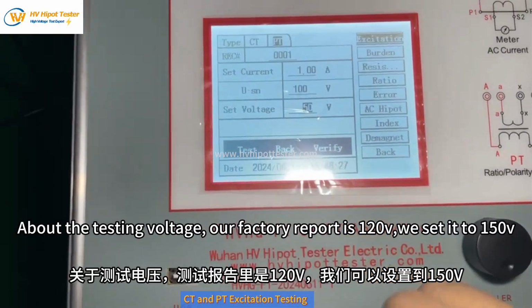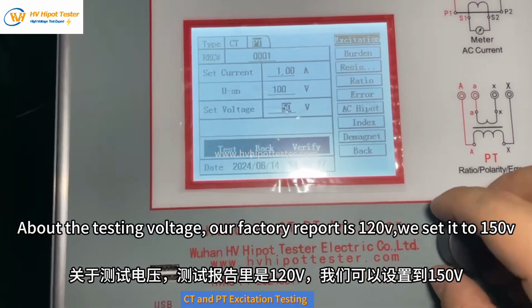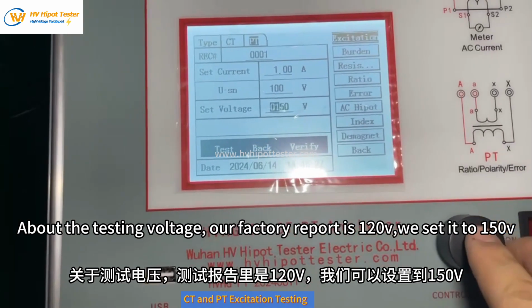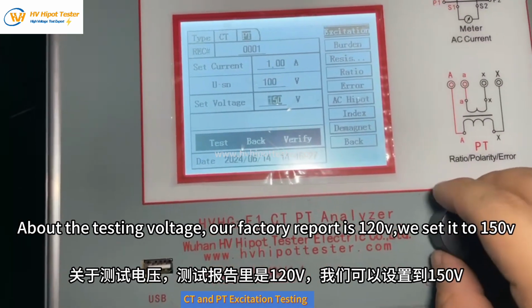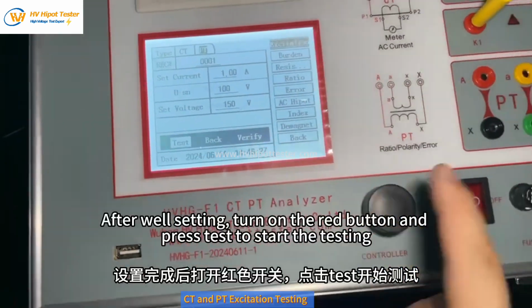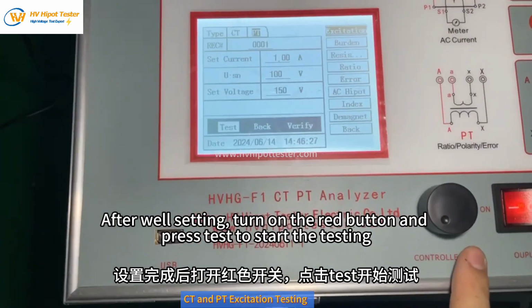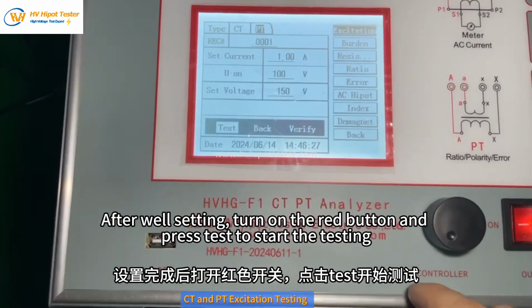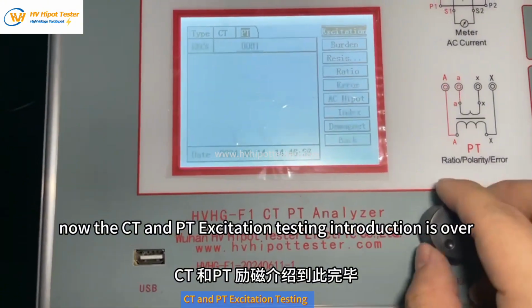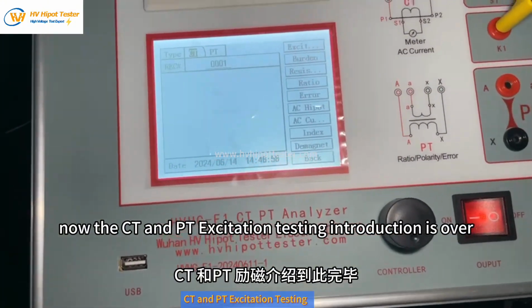About the testing voltage, our factory report is 120 volts. We set it to 150 volts. After well setting, turn on the red button and press Test to start the testing. Now the CT and PT excitation testing introduction is over.